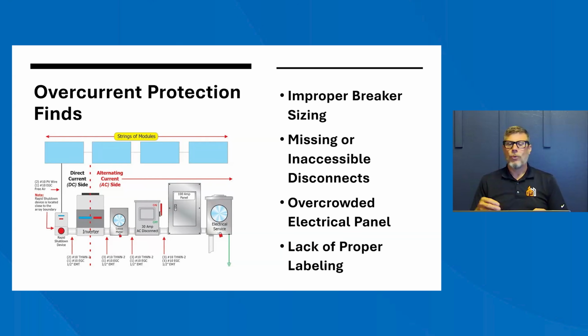You're going to see that where they've taken your breakers, the dual breakers, the tandem breakers, and they're just jamming them into the box to try to get as many wires in there as they possibly can. You see it very commonly on old homes where there's no more room left. Someone's just squeezed it all in, and now they have to try to force in all the solar panel stuff. That's going to create heat, and that's going to create issues with the system.